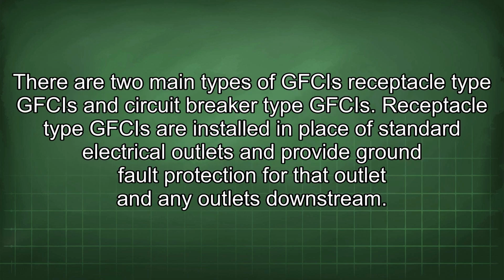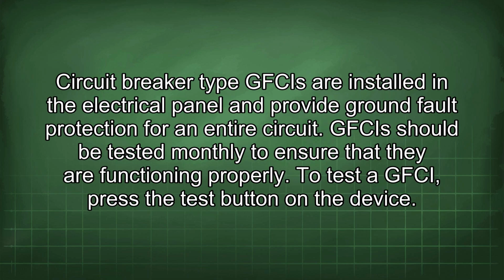There are two main types of GFCIs: receptacle type GFCIs and circuit breaker type GFCIs. Receptacle type GFCIs are installed in place of standard electrical outlets and provide ground fault protection for that outlet and any outlets downstream. Circuit breaker type GFCIs are installed in the electrical panel and provide ground fault protection for an entire circuit. GFCIs should be tested monthly to ensure that they are functioning properly.